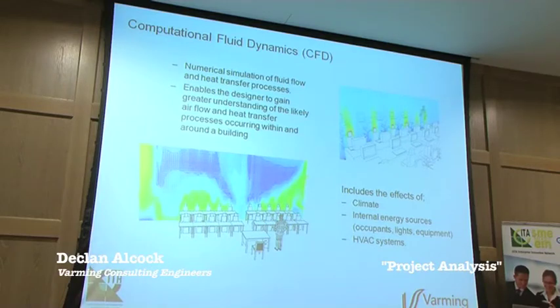And again, in the area of climate change adaptation, this is becoming a big issue with use of low energy equipment, effective use of thermal mass as well to mitigate the radiant component of the heat gains. It's not always possible to reduce the entire heat gain in a building, but you can push sections of it forward, and that way you reduce the coincident solar or the coincident heat gain at a particular time in the day. So the actual peak cooling load might not be reduced, but the duration of time over which it occurs can be.